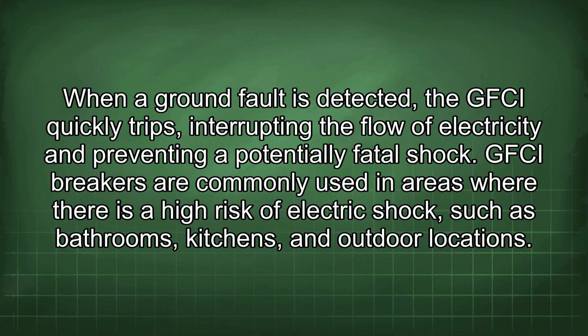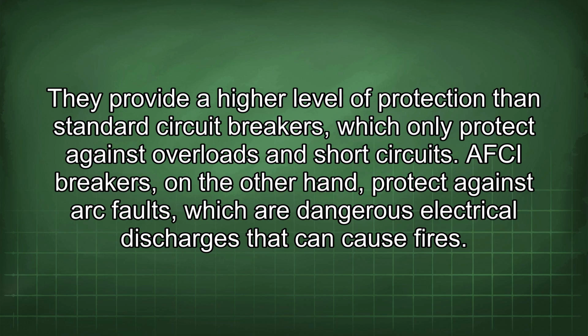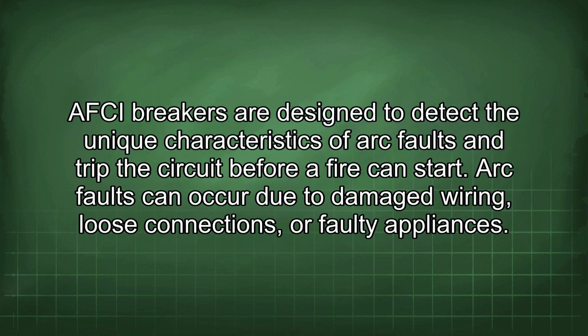GFCI breakers are commonly used in areas where there is a high risk of electric shock, such as bathrooms, kitchens, and outdoor locations. They provide a higher level of protection than standard circuit breakers, which only protect against overloads and short circuits. AFCI breakers, on the other hand, protect against arc faults, which are dangerous electrical discharges that can cause fires. AFCI breakers are designed to detect the unique characteristics of arc faults and trip the circuit before a fire can start. Arc faults can occur due to damaged wiring, loose connections, or faulty appliances.